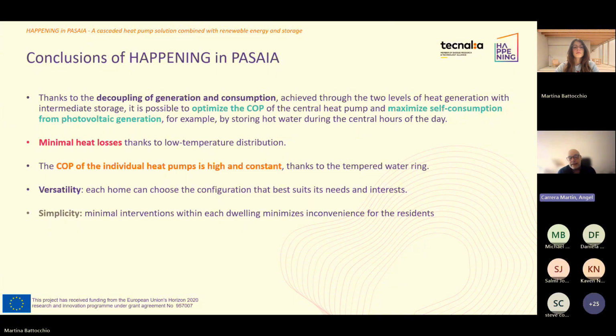The key we were looking at is simplicity: minimizing interventions in the dwellings, minimizing inconvenience for the residents, and reducing cost. We used a very simple distribution layout, with no balancing valves in the whole distribution loop — everything is balanced hydraulically — and we were able to maintain all the existing space heating emitters, which reduces cost a lot and is a benefit for everybody.